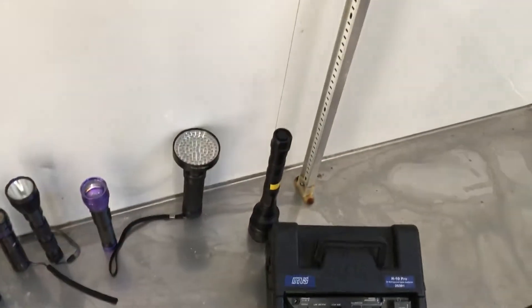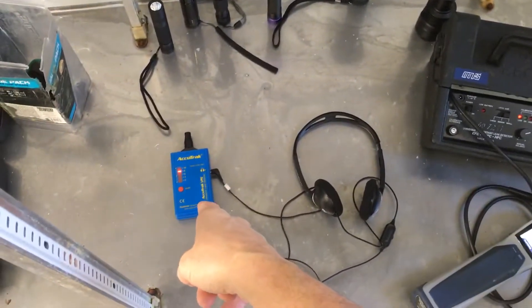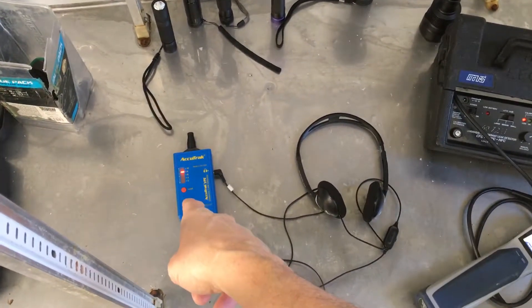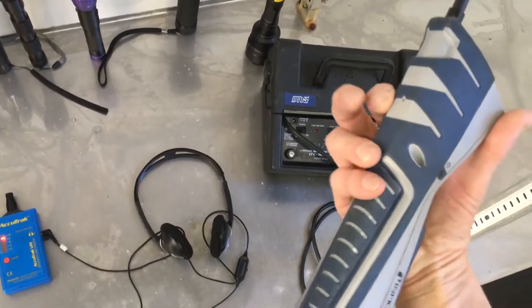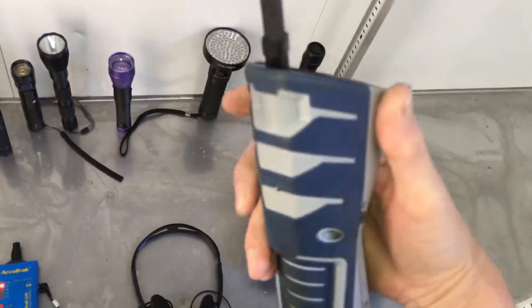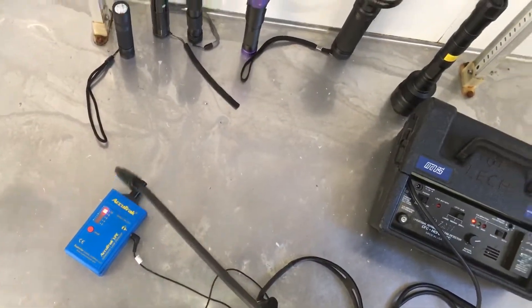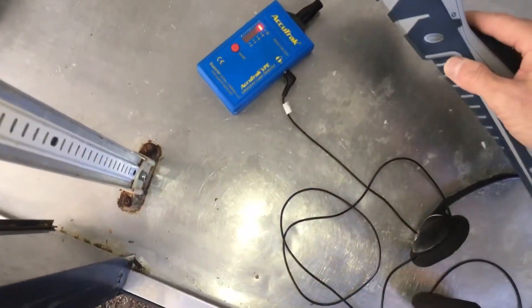We have a discrepancy with this device. These ultrasonic leak detectors are very sensitive to ambient sounds — certain frequencies can set them off. Right here you have a vacuum pump inside this unit sucking a vacuum through this little hole. Do not have any open vacuum sources. A lot of cars have vacuum bleeds on them for sensors, and if you're doing automotive work you'll have vacuum-operated ports and sensors and bleed ports all over the place. If you don't know that, you'll get very frustrated with this ultrasonic leak detector — and it's not the leak detector's fault. It's just a lack of knowledge.